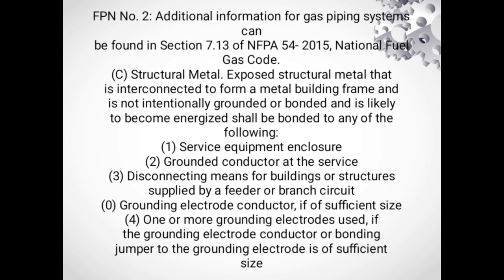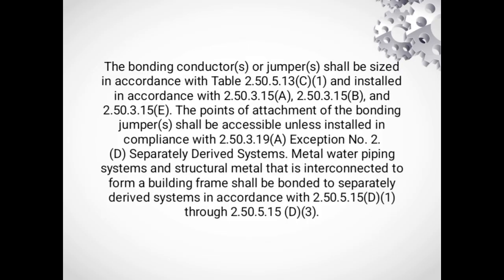Section 2.50.5.15 extends bonding requirements to other metal piping systems. This includes gas piping, compressed air piping, and other metallic piping systems that could become energized. The bonding conductor or jumper shall be sized in accordance with Table 2.50.5.13 and installed in accordance with 2.50.3.15A, 2.50.3.15B, and 2.50.3.15E. The points of attachment of a bonding jumper shall be accessible unless installed in compliance with 2.50.3.19A, Exception number 2. Separately derived system, metal water piping system, structural metal that is interconnected to form a building frame shall be bonded to separately derived system in accordance with 2.50.5.15D1 through 2.50.5.15D3.